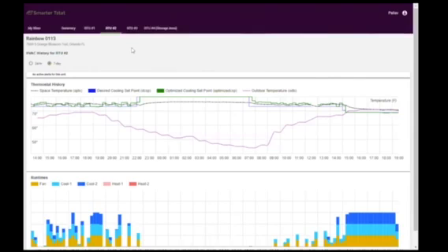And there's a reasonably good correlation between the capacity being provided and the power being used, with efficiency becoming approximately the same. And that allows us to minimize how much power is used. So it's a combination of the nameplate information providing us efficiency and capacity, and then watching the performance of the unit to see if it's close to the real world. And that's what the model learns.